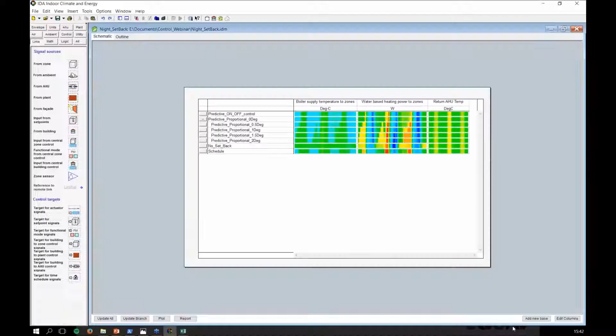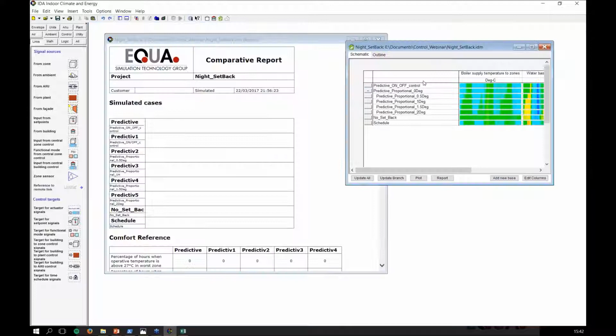Yeah, this is a pretty general question, I know. Are you facing any problem with the current control that you have? Because we have a motto: if it works, it's good. We only have humidity control. This is made with thermostats, which are on-off with some dead bands. It's not that sophisticated, so I don't know if you have any hint how to make it better. Here on the screen we have this option, VAV system with humidity control. Do you think this will help you? By default it creates a proportional controller which controls the ventilation signal based on the relative humidity set points that you create in the zone. Does that answer your question?